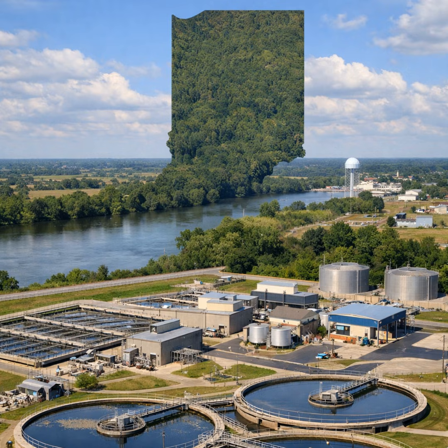So, for instance, when you have dissolved oxygen being pumped into the plant through aeration, if one of your blowers goes down and you're not feeding air into the system, then over time, if you don't get that corrected quickly, your plant can go septic and give off anaerobic conditions, anaerobic bacteria, foul odors, and hydrogen sulfide.